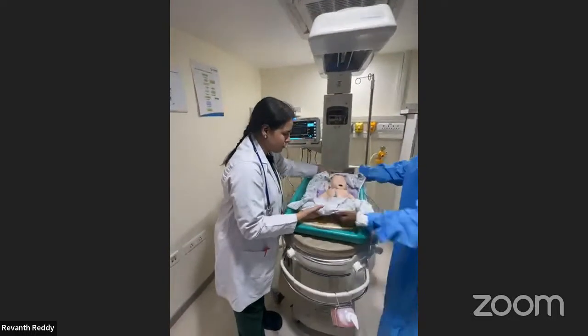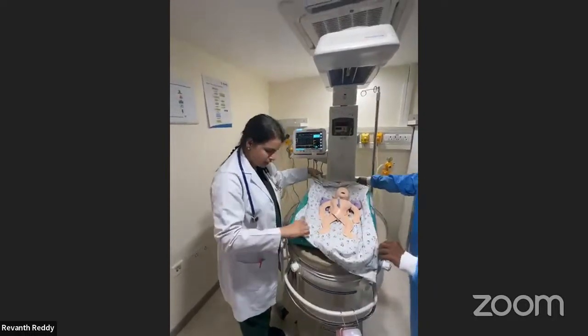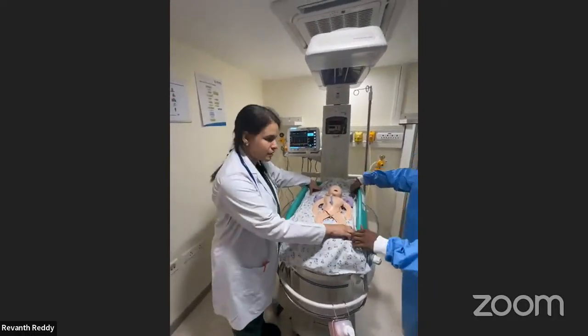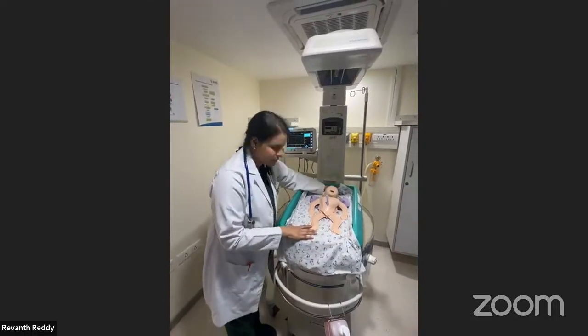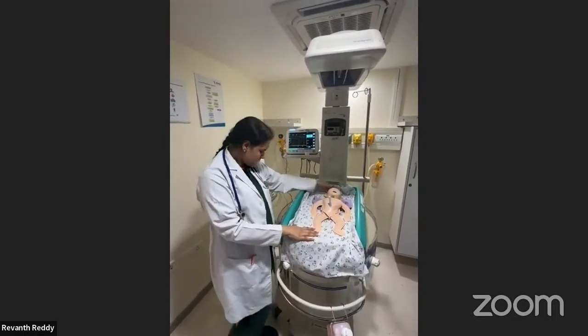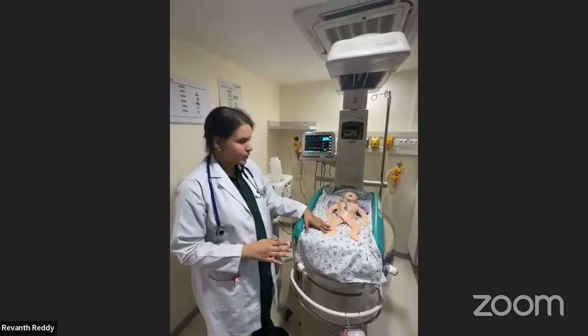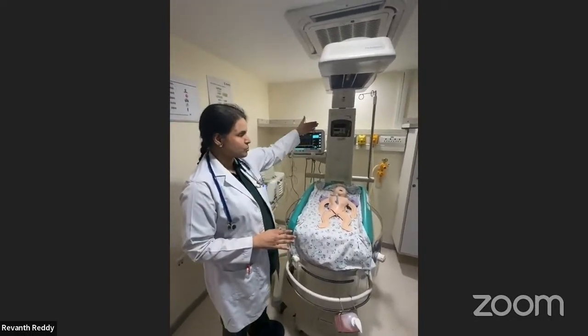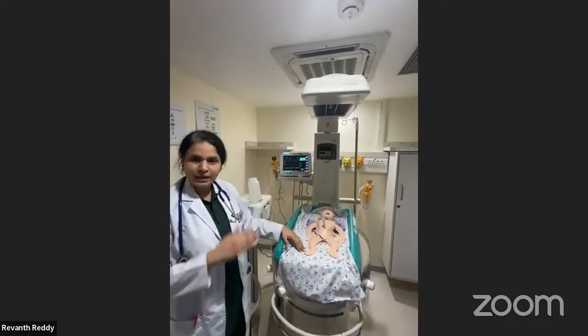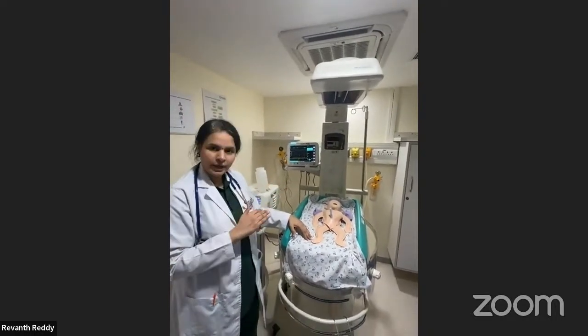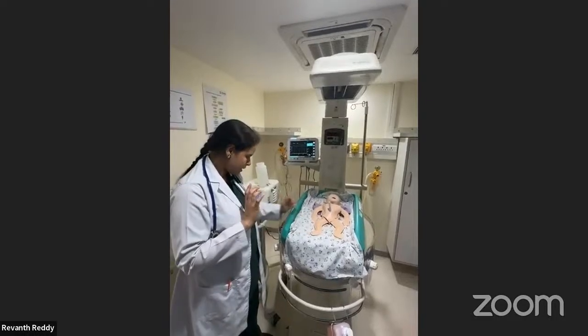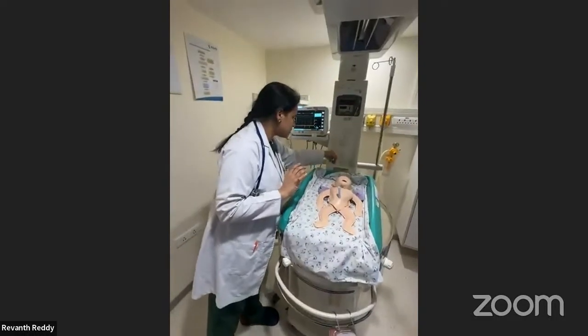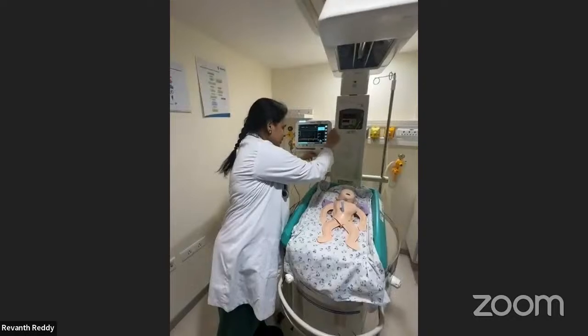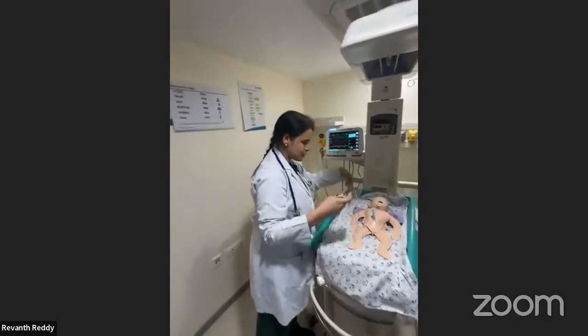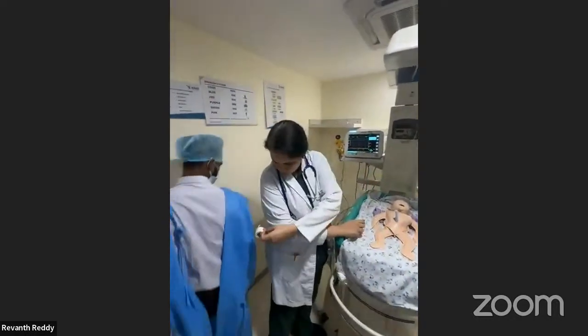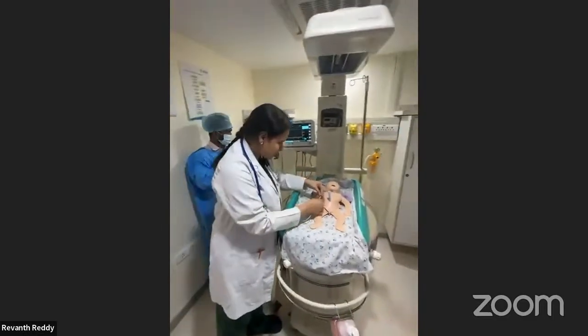Over this, we don't place the baby as it is. We cover these mattresses with a sterile or a clean cloth, and then we place the baby on top of it. Now, during the induction phase, the radiant warmer should be switched off. The temperature of the baby gradually drops from 36.5 to 33 to 34 degrees Celsius. How do we monitor this? We will have to continuously monitor the temperature of the baby using the skin temperature probe. Skin temperature of the baby.